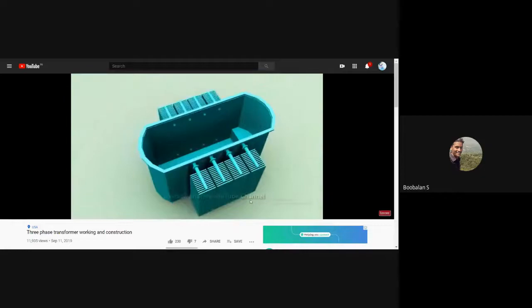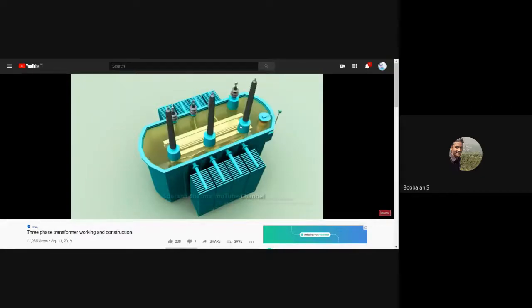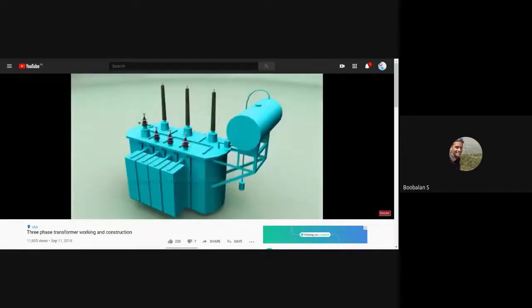The tank consists of radiator wings and oil is filled inside the transformer tank so that the complete assembly remains immersed in the oil. The transformer is completely filled with mineral oil. The transformer unit also consists of a conservator tank installed over the main tank. The main tank and the conservator tank are connected through a pipe and a Buchholz relay.